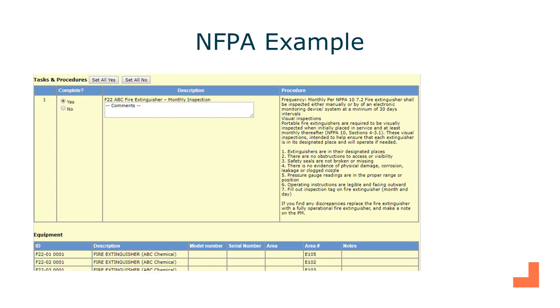So this is an example of what we mean when we're talking about NFPA. This is an example of our preventive maintenance action for our fire extinguishers. What we do is we actually pull the requirement right out of NFPA and put that in our procedures, so our mechanics know exactly what they're supposed to do, and we're tagging it back to a national standard.